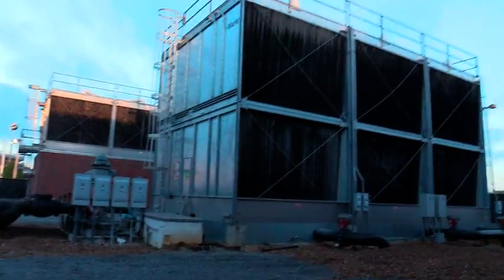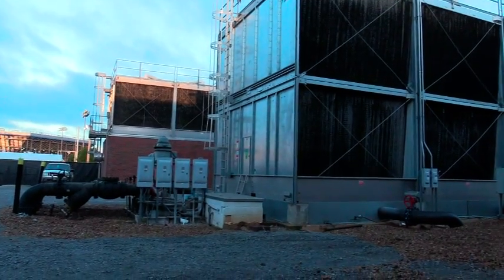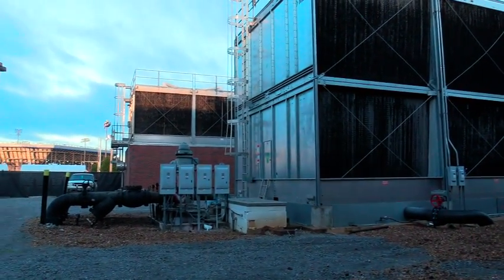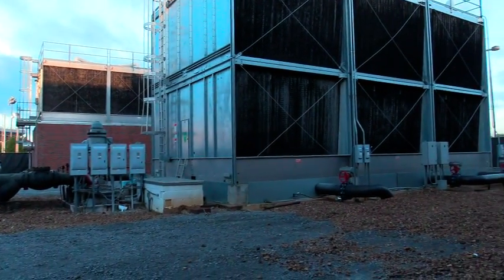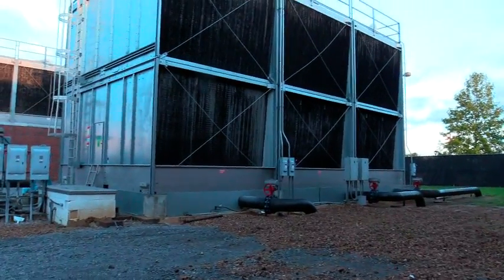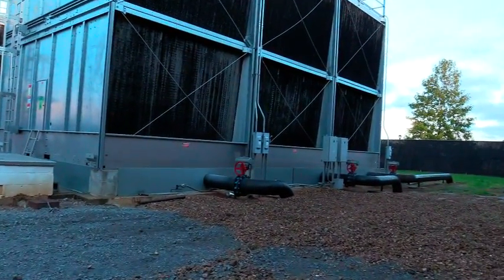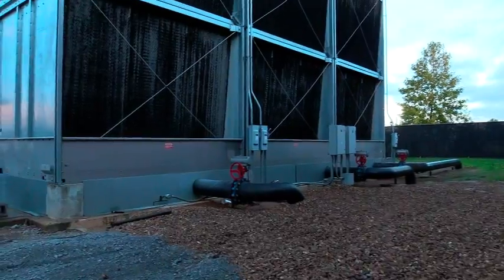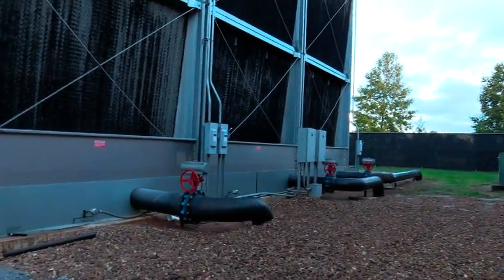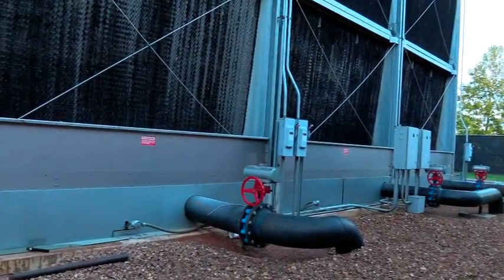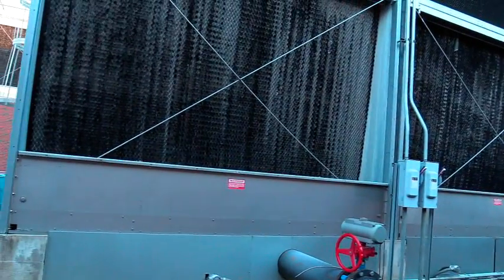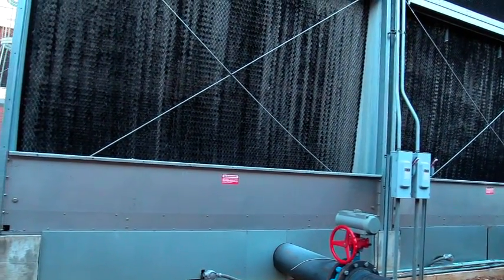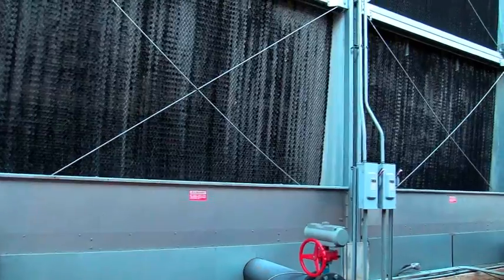Sometimes you have more problems with these outside isolation valves than the inside ones. They're a pain. The automatic ones can also be put in hand, and sometimes you have to. But when you turn that chiller off and have another one running, you have to make sure you do it, because you'll have water running through here with no fan control, so the water gets hot, and that causes the chillers to surge.